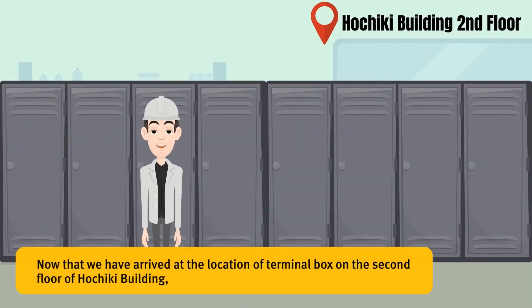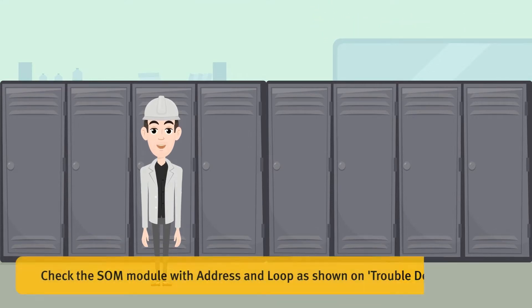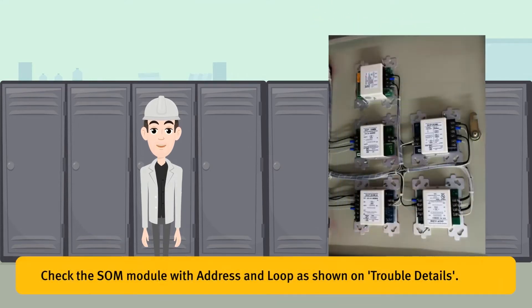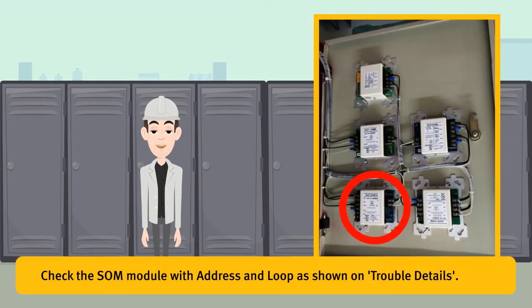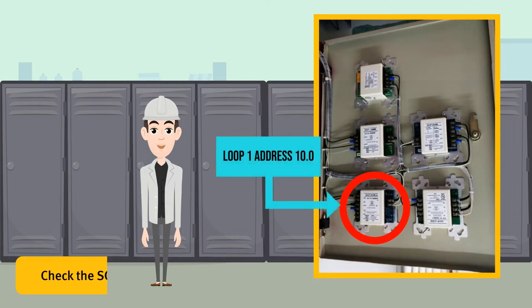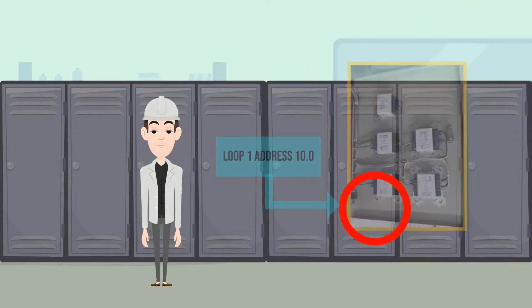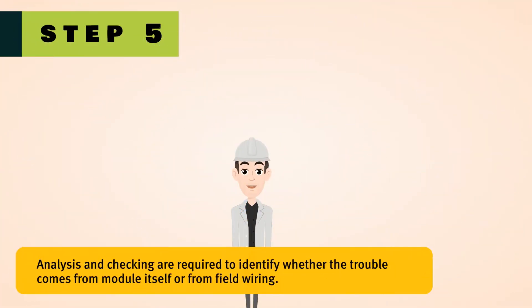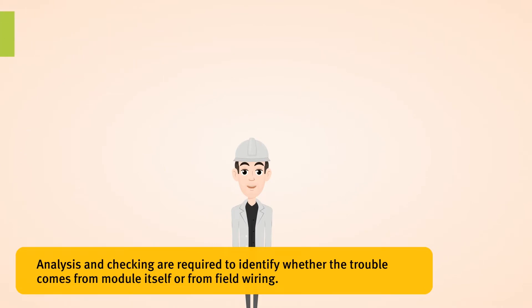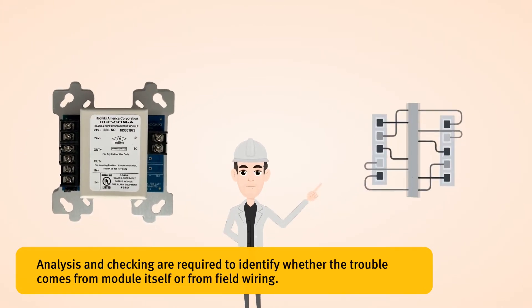Now that we have arrived at the location of the terminal box on the second floor of Hochiki building, check the SOM module with the address and loop as shown on the Trouble Details. Analysis and checking are required to identify whether the trouble comes from the module itself or from field wiring.